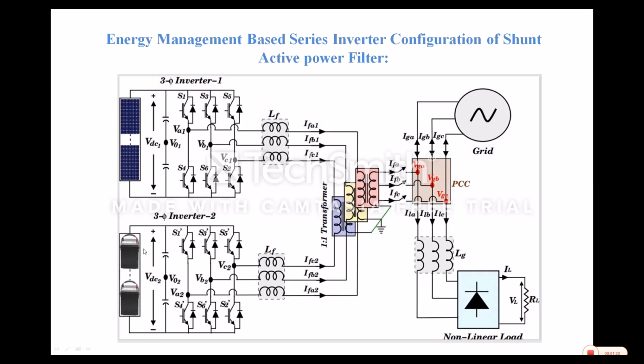The main advantage of the series inverter configuration is that the requirement of the DC link voltage is half that of a single three-phase inverter configuration. Coming to its operation, both inverters will switch such that they compensate the harmonics drawn by the non-linear load and also inject the active power, and they are controlled individually. This inverter is controlled independently with respect to the other inverter.